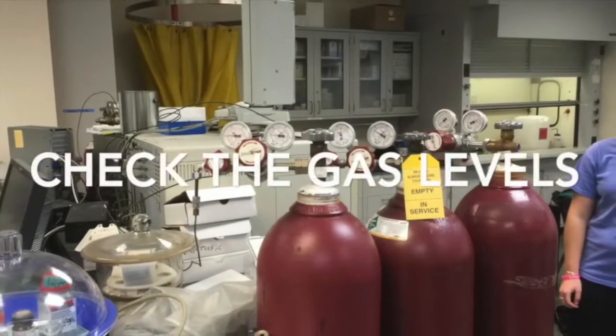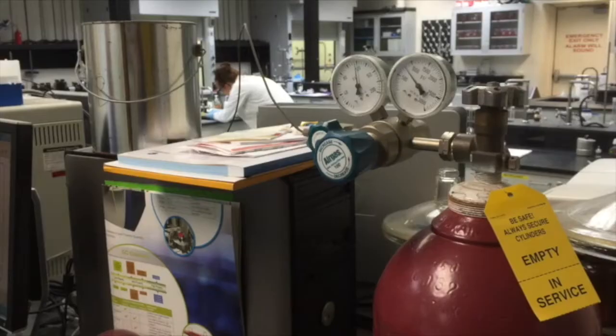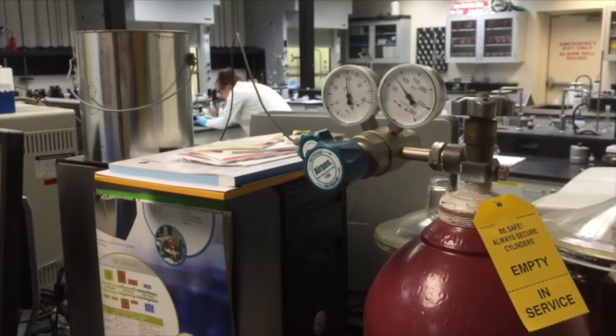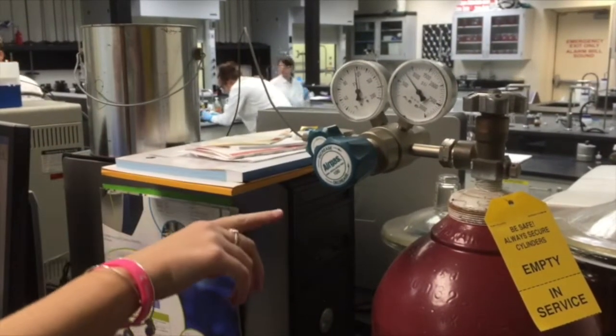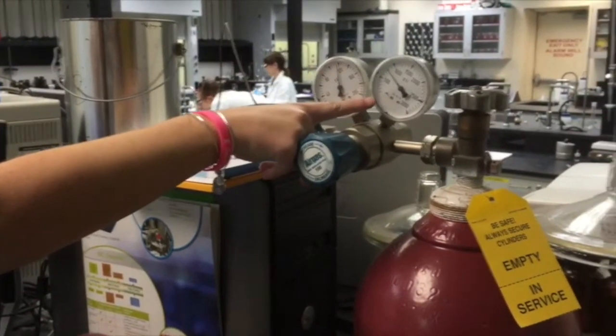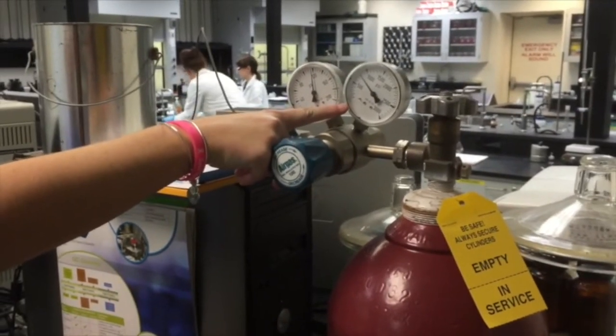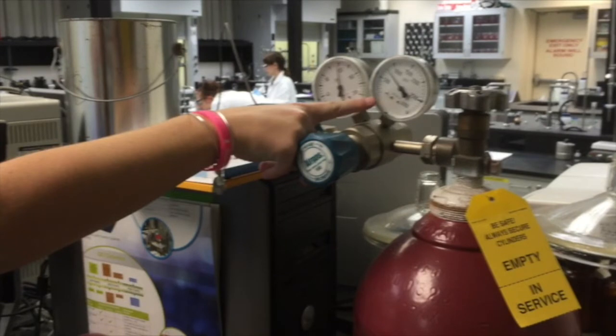So before you get started running the GC, one of the first things you want to do is check the gas levels. You're going to come up to the GC and look at the regulator and look at this first gauge. If the pressure there reads less than 500 psi, you need to let me know so that we can change out the gases. Make sure to check all four gas tanks. There are three on the left and there's one on the right.